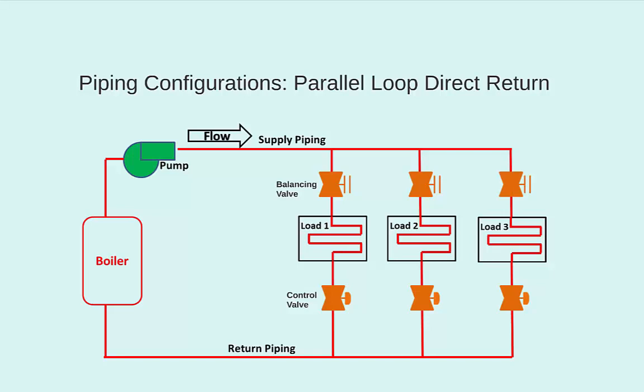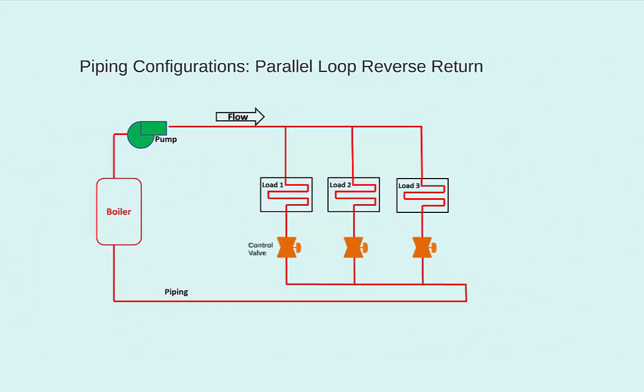So, we often see another style of the parallel loop piping configuration installed. It is called the reverse return configuration. In this configuration, the flow leaving load 1 does not directly head back to the pump. Instead, it goes to pick up the flow coming out of the other coils before it heads back to the pump. In this configuration, it is pretty hard to determine the path of least resistance. For the flow going through load 1, it will have to travel through roughly the same amount of piping that the water flowing through load 3 would have to follow. Thus, the layout is inherently more balanced to begin with.